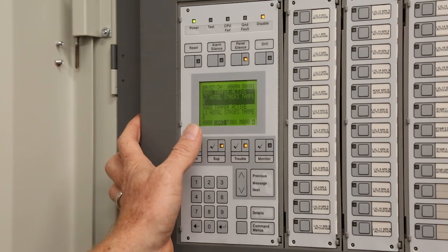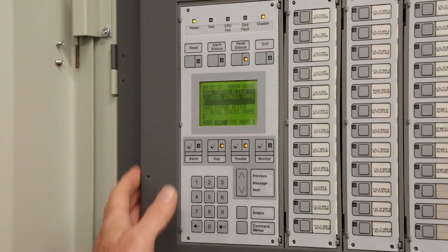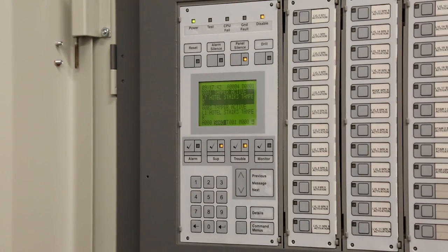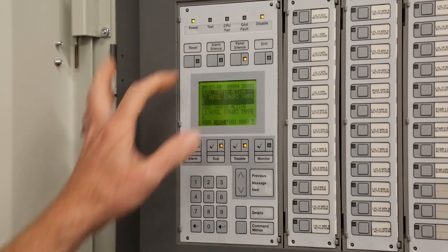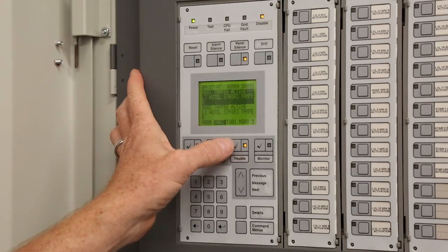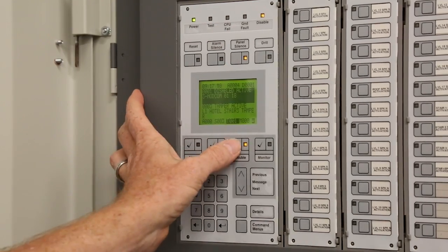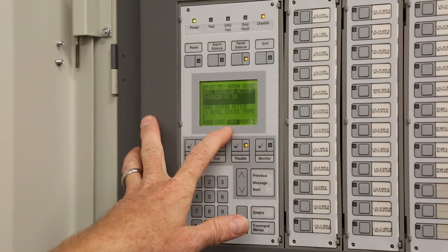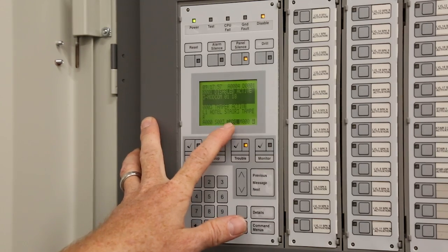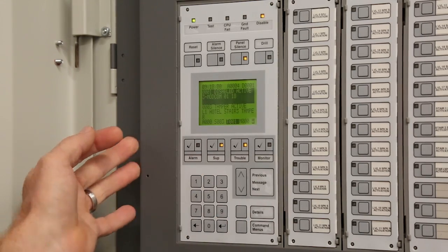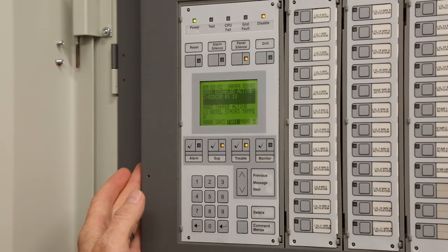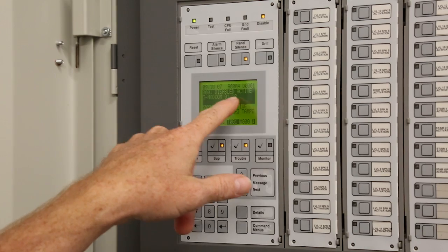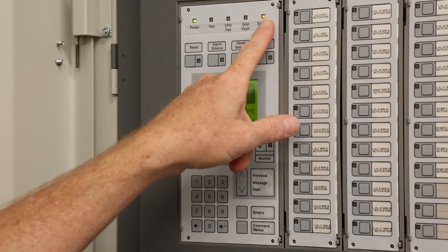Troubles would be any abnormal condition, and it could be that the device is not responding. Could be an open circuit, or it could be like we have right now, disabled. For instance, right now, you can pull up your troubles by just hitting the button right there, and you can scroll up and down. Right now, if you see there's a T right there that represents troubles, there's only one. It says Modcom. That's because I have the dialer offline, so it won't report right now. And also, if we have anything disabled, like I have this disabled, it says disable active, and your disable light's on up here, okay?